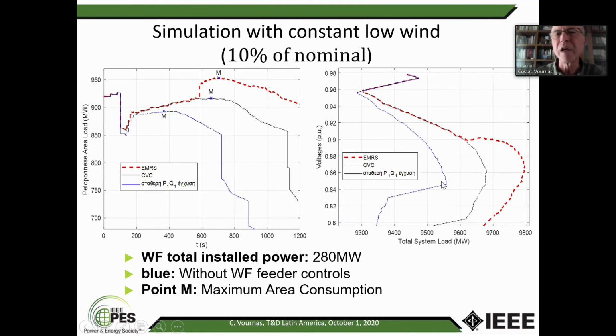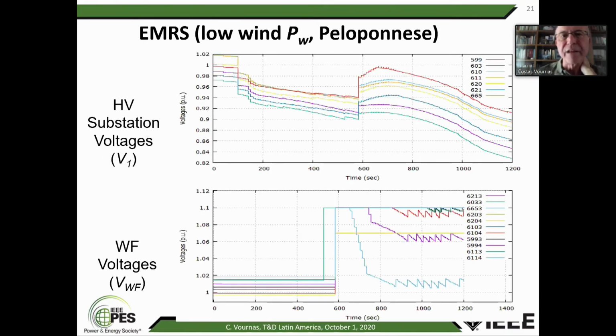And you see on the right, the total system load of the Hellenic system. And you see again the increase that you get from the 11 wind farms in Peloponnese, first with constant voltage control and the support by the capacitors, and then the red curve, which is the emergency reactive support. So you can get from little farms a very large result. And here you can see the substation voltages on the primary, and that's the high voltages of the 11 farms. And here you see the wind farm voltages.